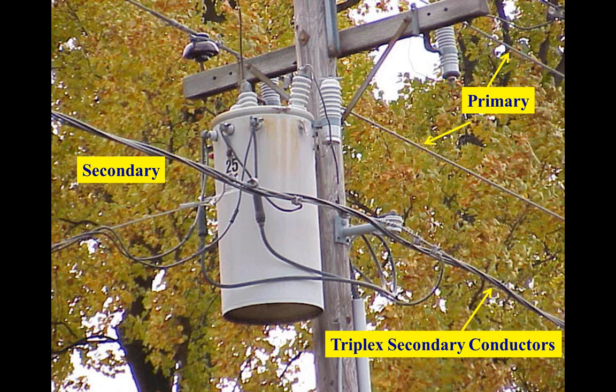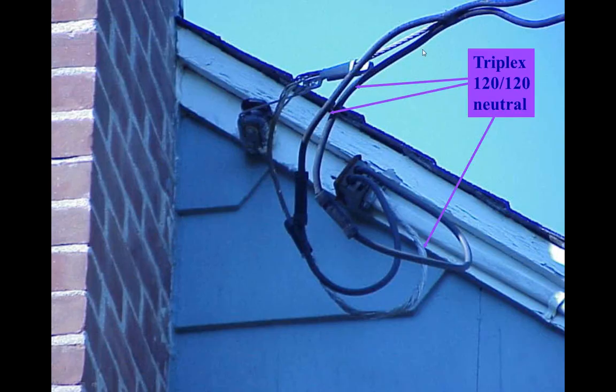All right? This is where your secondary attaches to your house. There it is coming over. The bare neutral is tied off through a wedge to an insulator so it doesn't have a path to ground through your house. The insulator insulates that. Here are your two hot legs. Your hot legs are coming in at 120 volts. They go through your weatherhead, and they go down to your service panel.